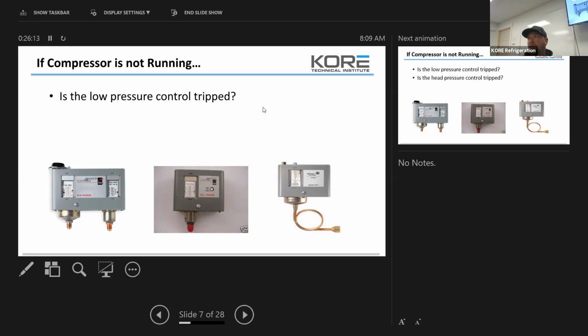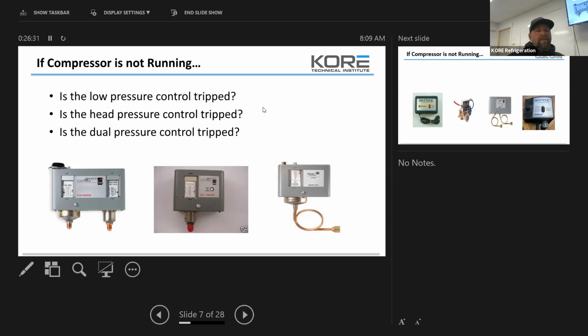So just identify those. You may not have this type of switch. You may have more of an encapsulated switch, but most compressors have safety switches in play. So yeah, low pressure, head pressure. And then when you're dealing in low ambient conditions, you're going to deal with a motor master or a fan cycling control or a head master. Okay. So is the head pressure control tripped? Is the dual pressure control tripped?